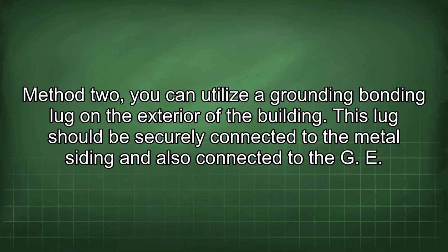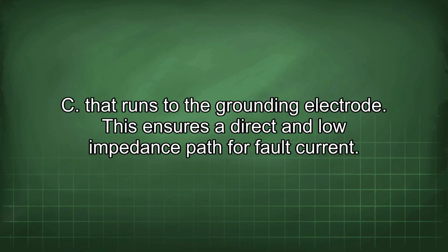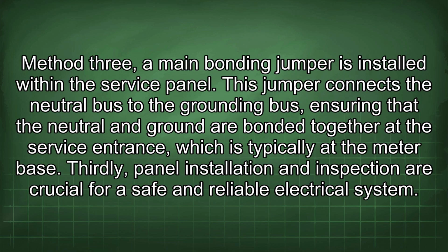Method 2. You can utilize a grounding bonding lug on the exterior of the building. This lug should be securely connected to the metal siding and also connected to the GEC that runs to the grounding electrode. This ensures a direct and low impedance path for fault current. Method 3. A main bonding jumper is installed within the service panel. This jumper connects the neutral bus to the grounding bus, ensuring that the neutral and ground are bonded together at the service entrance, which is typically at the meter base.